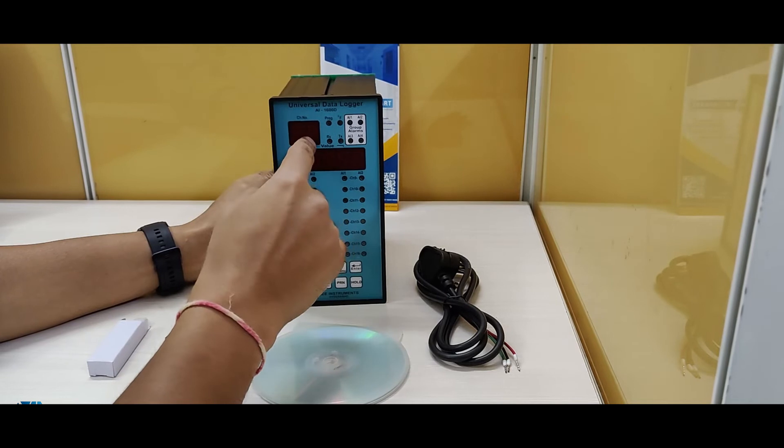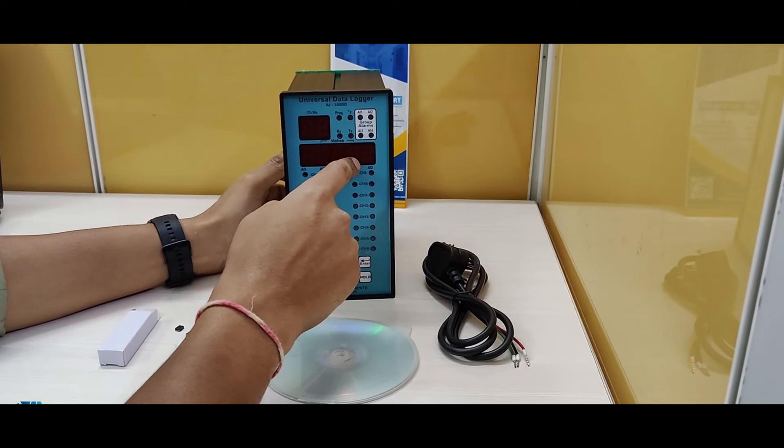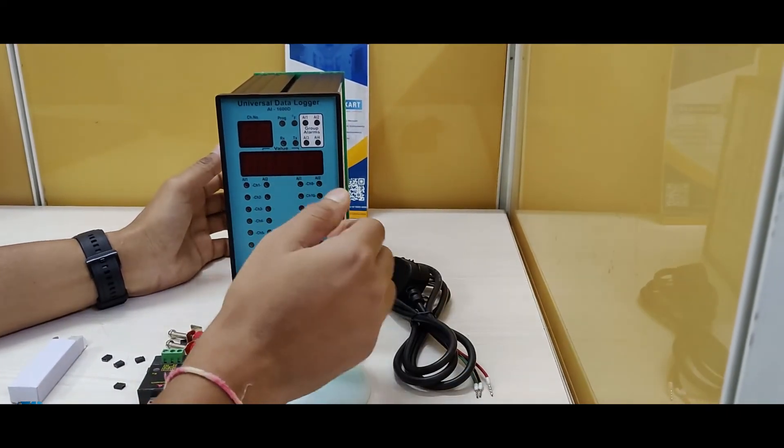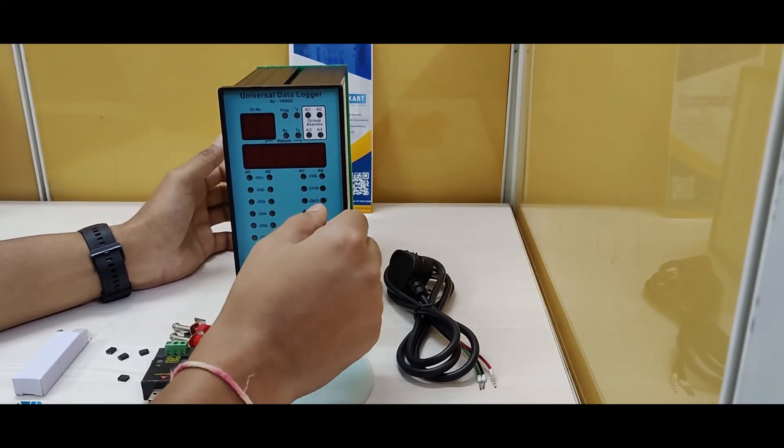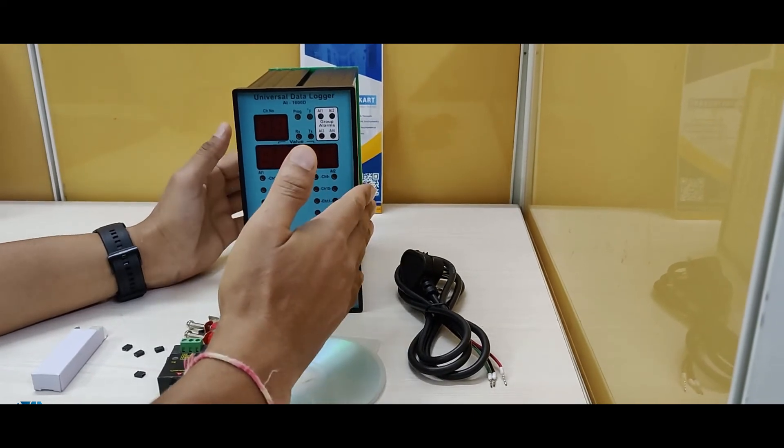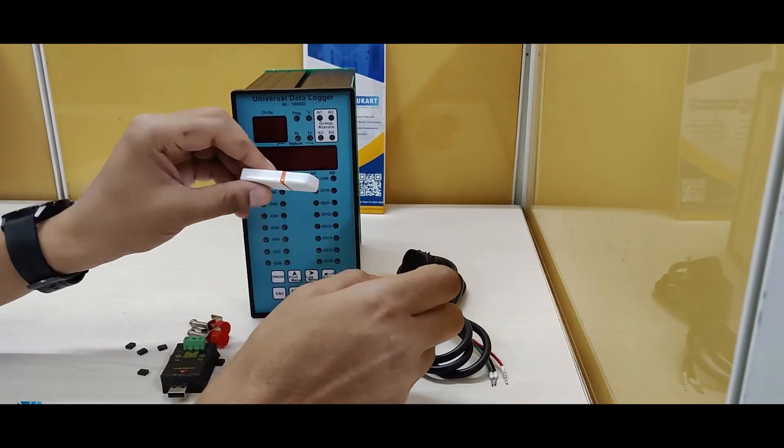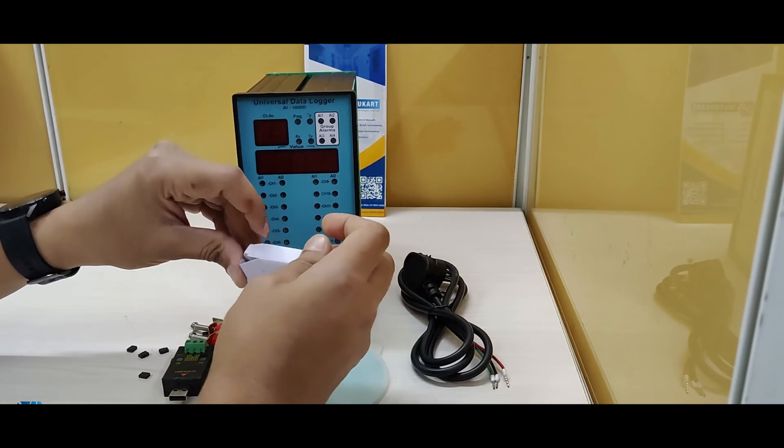Front, as you can see, is the LED display seven segment. For any kind of channel violation you also have a relay NO/NC so that you can control any kind of motor or pump or fan or any other devices. This particular data logger also comes with the USB software so that you can configure that into the PC.